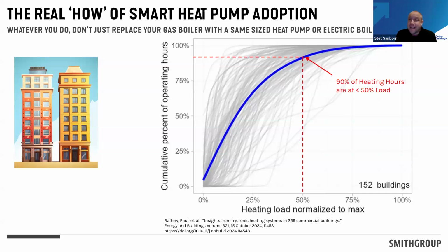I'll say that again: 90% of hours we're operating at less than half of the design load of that boiler plant. For those last few hours at the top, applying a heat pump there means buying expensive equipment that's almost never going to run. This is the first barrier we want to overcome in our project.